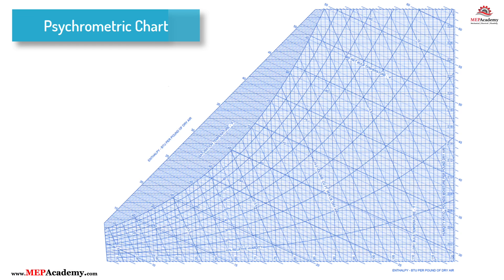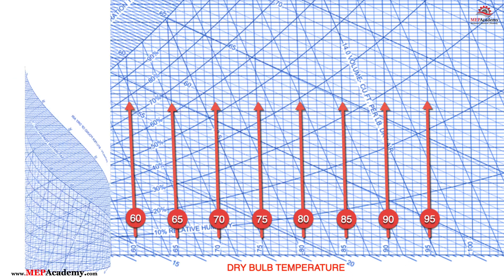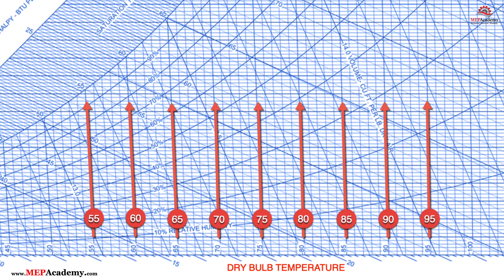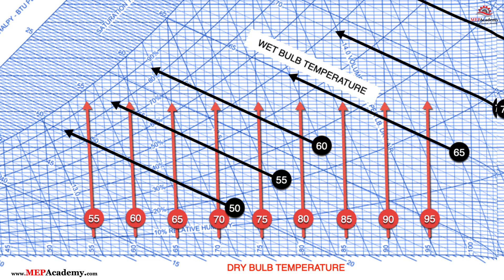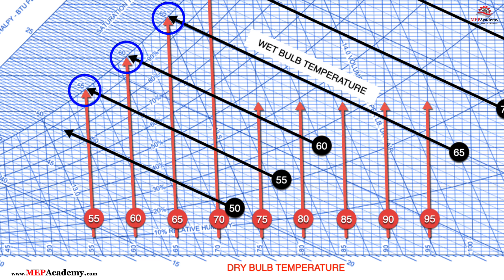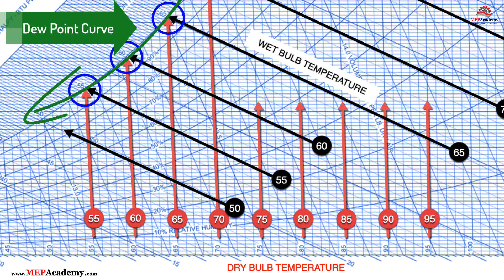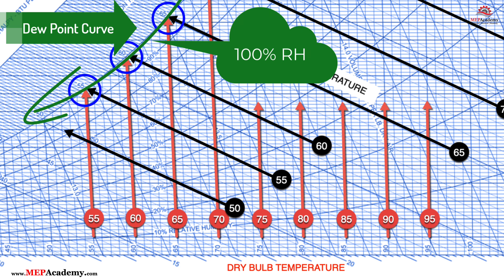On a psychrometric chart, the dry bulb and wet bulb temperatures are key variables. These values help us understand how much moisture the air contains and how it affects heating, cooling, and dehumidification. The dew point is directly related to both temperature and humidity. The dry bulb temperature runs vertically up from the bottom, while the wet bulb temperature runs diagonally. When the dry bulb and wet bulb temperatures are the same, the air is completely saturated and they meet at the dew point line on the chart.